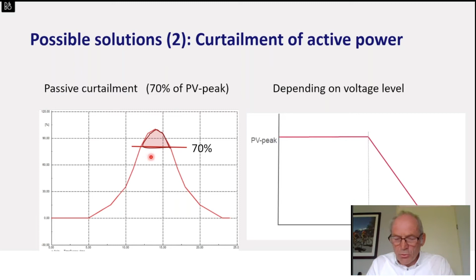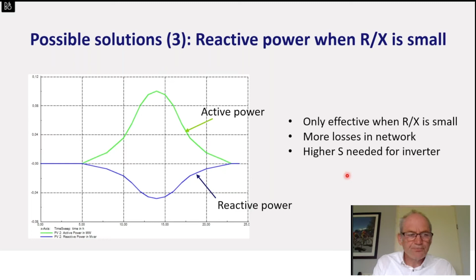Another solution is reactive power. But reactive power only works quite effectively when the R over X ratio is quite small. When you have a low voltage network with a lot of resistance, reactive power doesn't work very well, and it will also give you more losses in the network because you are drawing more current. You also need a higher apparent power of your inverter. But when you have a medium voltage network close to the transformer, where the R over X ratio is quite small, it could be a good solution.